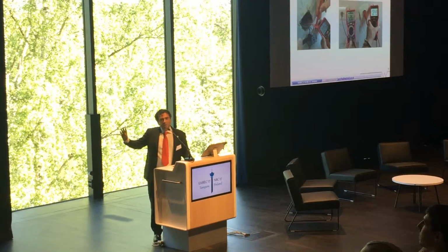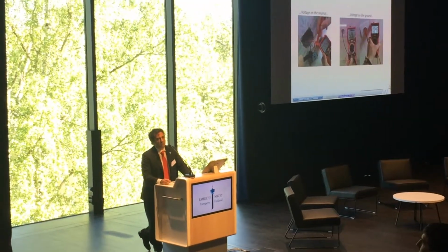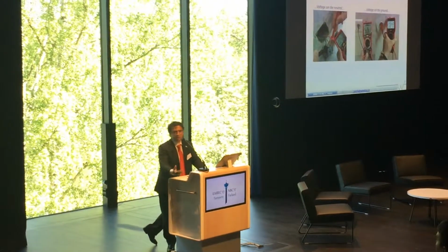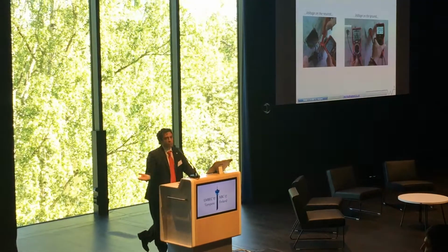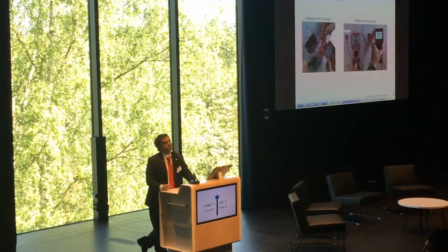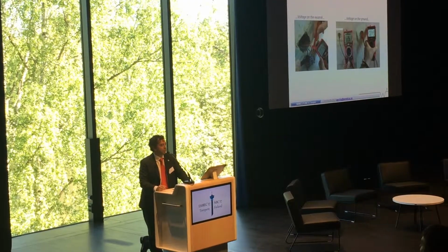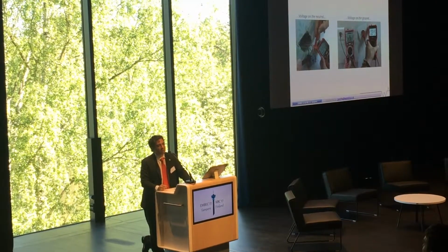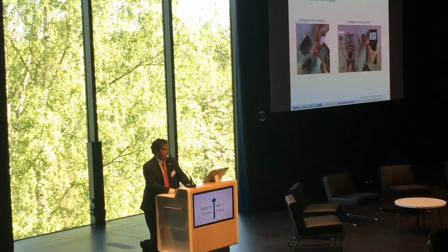Now, we did this field analysis. We visited 5 hospitals in Benin. We started from Benin because there was a charity of surgeons going there for 15 years, so it was easier for us to go there. And that's what we found. So this is the voltage on the neutral, it's 5-6 volts. The voltage on the ground was 85 volts. Now, it should be 0, for those of you who are not familiar with those numbers, okay?